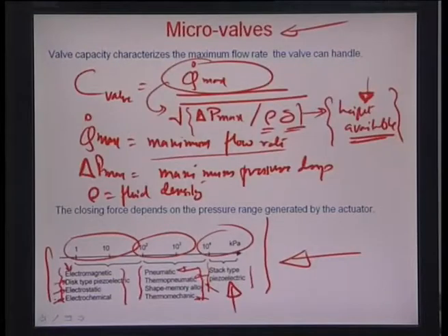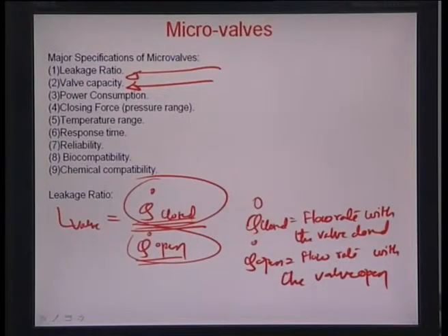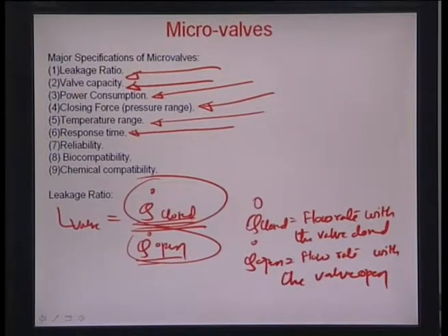There are some other performance factors which include what kind of power is consumed by the system, what the closing forces are in terms of pressure ranges which you need for the valve to fully close, and what temperature ranges you can use the valve in. These are some of the specifications if you design such valves. What is the response time? It is a big criterion: how quickly the valve can open and close a particular flow. Is there any reliability issue? Whether the valve operation is unique and repeatable every time is a very important design paradigm.